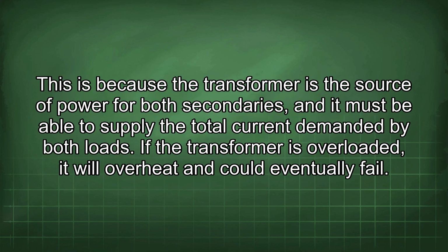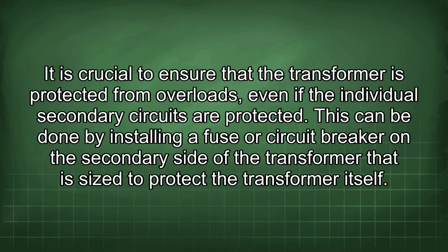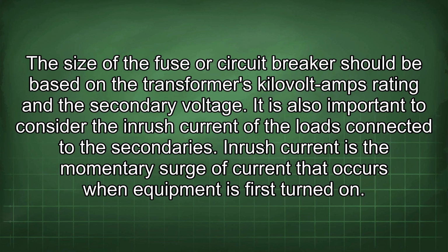This is because the transformer is the source of power for both secondaries, and it must be able to supply the total current demanded by both loads. If the transformer is overloaded, it will overheat and could eventually fail. It is crucial to ensure that the transformer is protected from overloads, even if the individual secondary circuits are protected. This can be done by installing a fuse or circuit breaker on the secondary side of the transformer that is sized to protect the transformer itself. The size of the fuse or circuit breaker should be based on the transformer's kVA rating and the secondary voltage. It is also important to consider the inrush current of the loads connected to the secondaries.